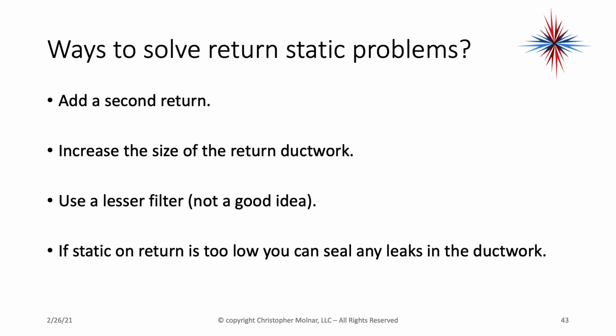Ways to solve a return static problem? Add a second return. Increase the size of the return ductwork. Use a lesser filter, even though I don't like that idea. Okay, because the better the filter, the cleaner the equipment's going to stay. If static on return is too low, go seal the leaks.